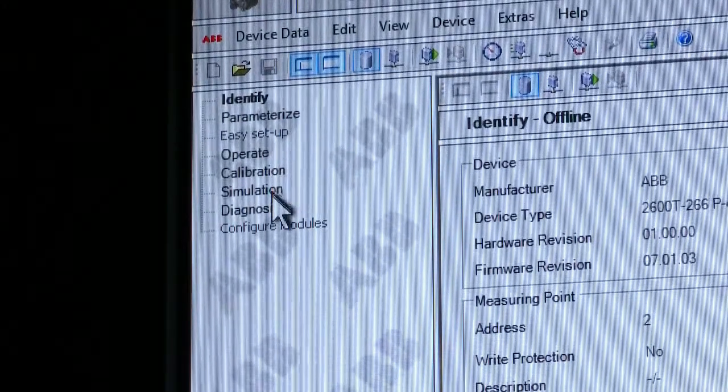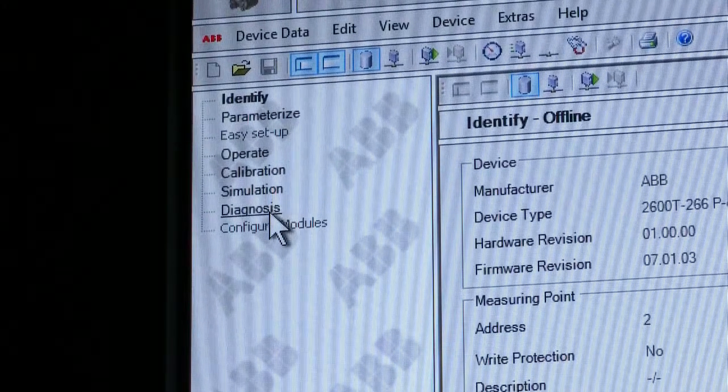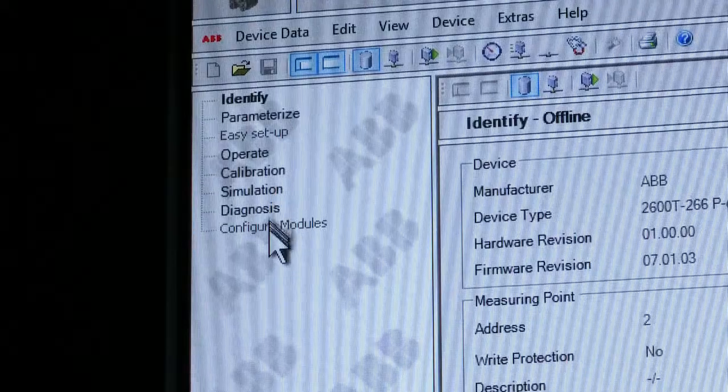If we determine there is a fault with a particular instrument through the intelligent data, we can simply right-click, and assuming a SAP or Maximo computerized maintenance system is connected, we can generate electronic work orders directly from the right-click. We're also able to access active work orders, spare parts, and work order history directly from the HMI.